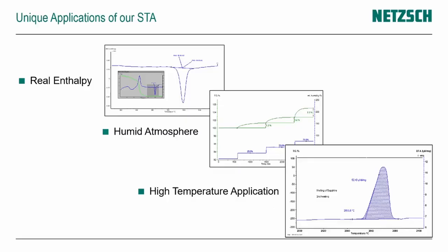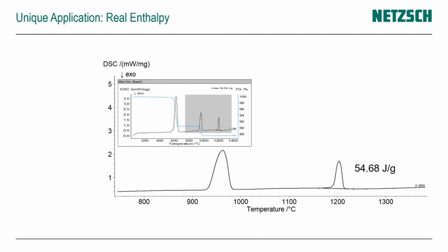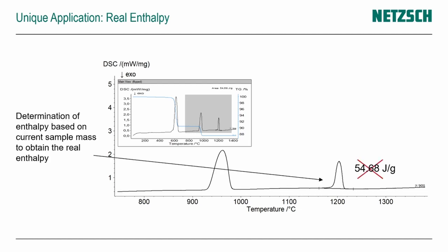The STA has some unique points compared to dedicated systems. The first is real enthalpy. In normal DSC analysis, we look at phase transition effects, for instance a phase transition around 1200°C. These high temperature phase transitions are mostly combined with a mass change that happened before. In a dedicated DSC, measured enthalpy values are always related to the starting mass of the measurement. However, if the sample changes mass during the measurement, this value is incorrect, because at the point of transition the sample mass is no longer the starting mass. The STA measures mass simultaneously to the DSC signal, and therefore knows at every point the real mass of the sample, allowing it to determine the real enthalpy of the phase transition.